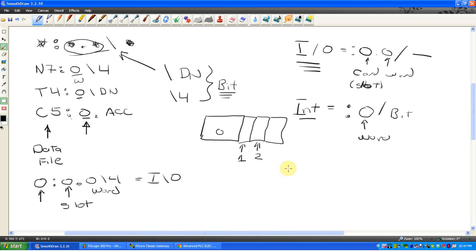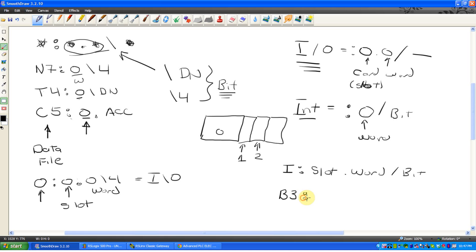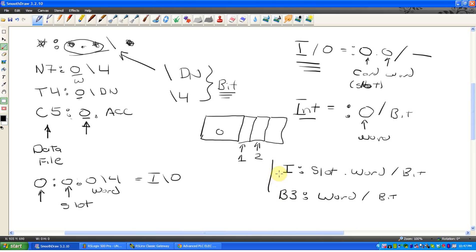So to write it out completely, if I were to say I colon, that's input colon, because it's real world, it really truly exists, the terminal screw on the PLC, it's going to go with slot dot word slash bit. That would be the same if it was O. Those are the only two options. Anything else, for example, B3 is the binary data file, and if I were to say 4 slash 0, I'm saying word 4 slash bit 0, right? So that's sort of the addressing model that exists.